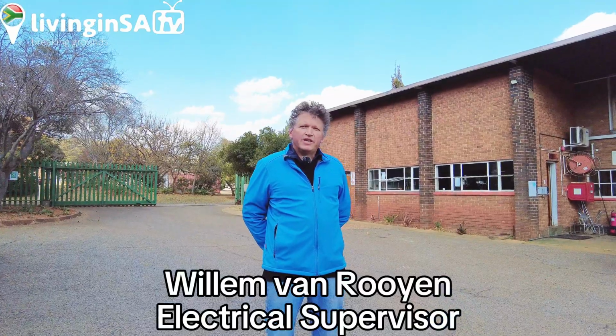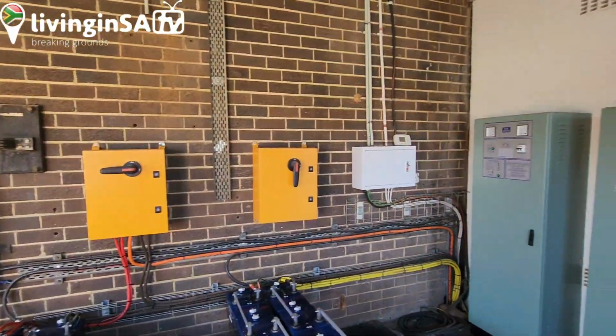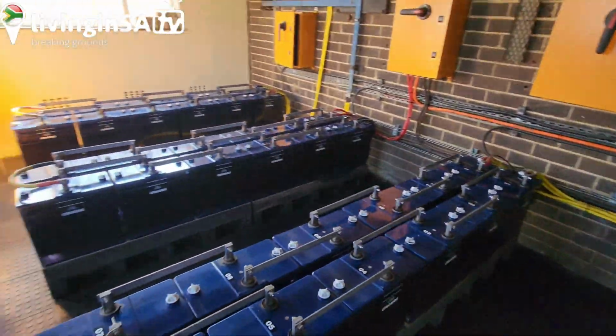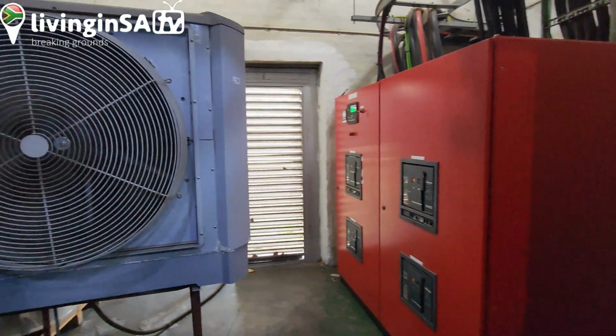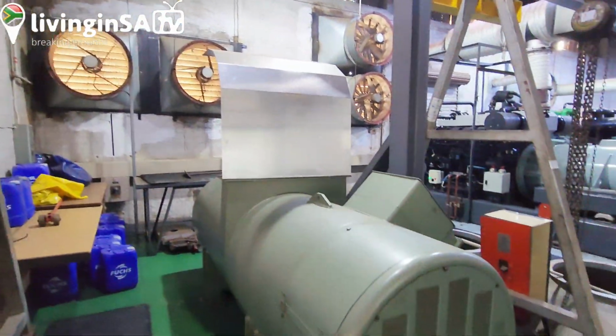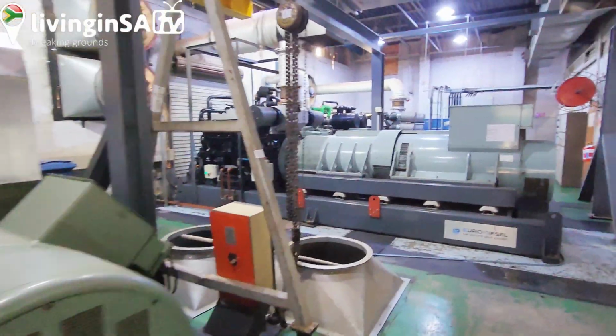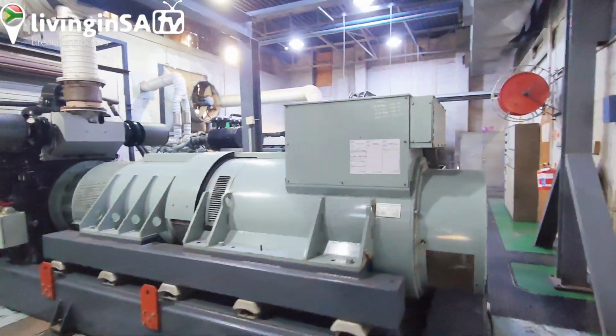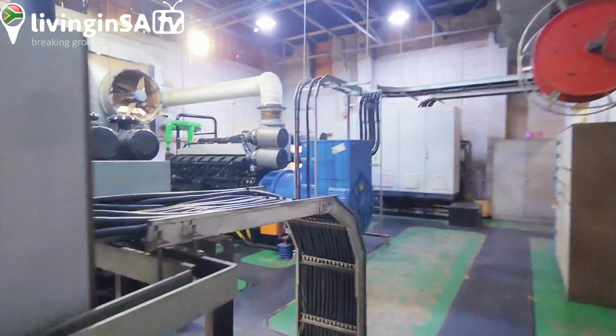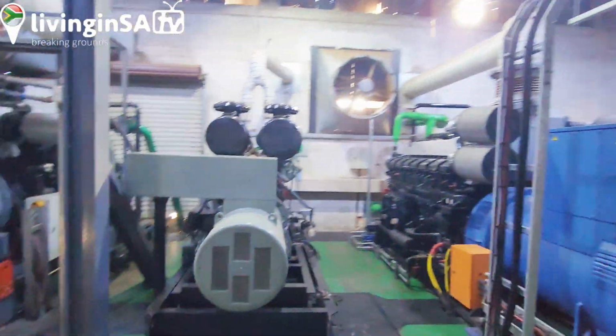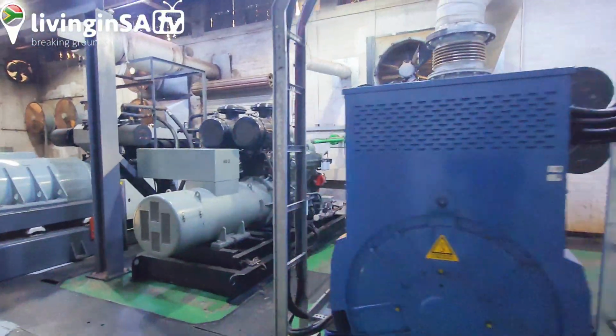Hi, I'm the electrical supervisor on site here at a power station for SANSA. We are required by our contracts to have our UPS available 99.99% of the time for power availability. Also, the purity of our power is better than Eskom can supply. So we use a Euro diesel system as our primary backup supply, a dynamic UPS with diesel generator backup. Once we lose reliable power or have quality issues with Eskom power, this system takes over and gives us clean power.